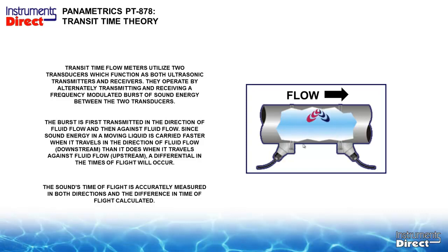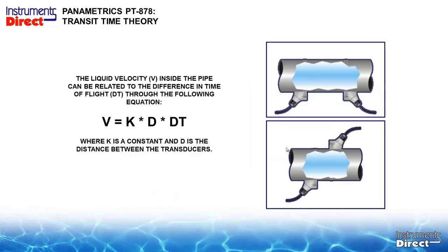The sensor on the right hand side will send a sound burst across the pipe, ricochet off the back wall, but remember the flow is going from left to right. It will take a longer period of time. The greater the differential, the faster the flow rate. So again, the same type of functionality, and we have different configurations. The picture in the lower right hand corner is the man in the rowboat, which is referred to as the Z, or the single path for the GE products, and the one in the upper right hand corner is referred to as the dual path, or the V configuration, and they're usually relegated based upon pipe size.